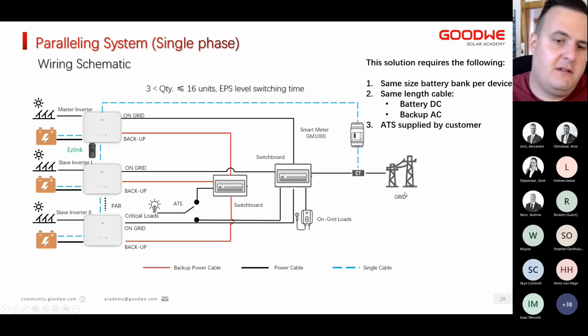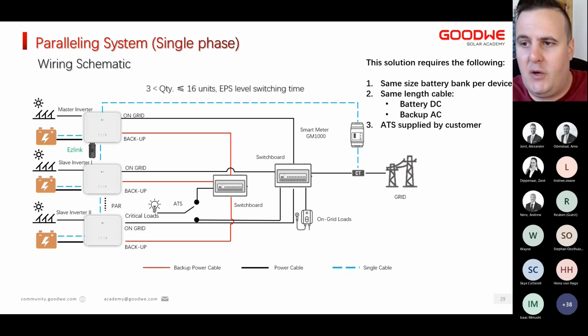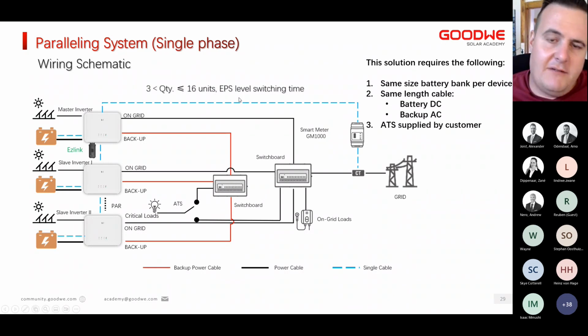I know currently this is not the most ideal situation, but in a single phase system, having more than 3 6 kilowatt units paralleled is quite big for single phase and is most likely not really going to happen. But this solution is available. Please note that is EPS level change over time. The ATS normally switches within 20 milliseconds to 100 milliseconds, and that causes the delay. So computers and things like that will shut off during that change over time.